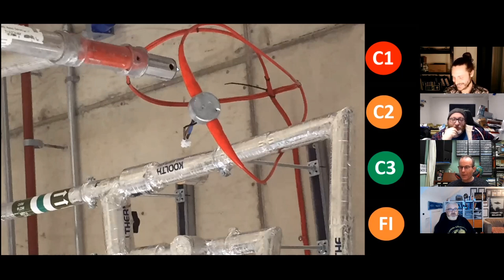So I think it would be sensible to accept that this is a construction site, but based on my engineering judgment, if it was a work in progress and that system was decommissioned, de-energized, I would say, you silly idiot, you've got the pipe through it. You'll have to disconnect that pyro from the box and redress it down and tuck it out of the way, to prevent it getting damaged. But if that system is being commissioned or in part commissioned, then I would see to that. But for me, it's an FI/C2 on my coding.